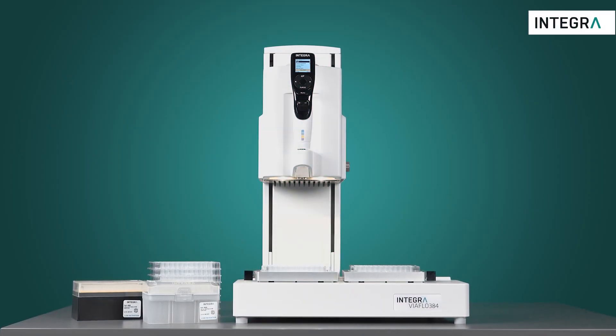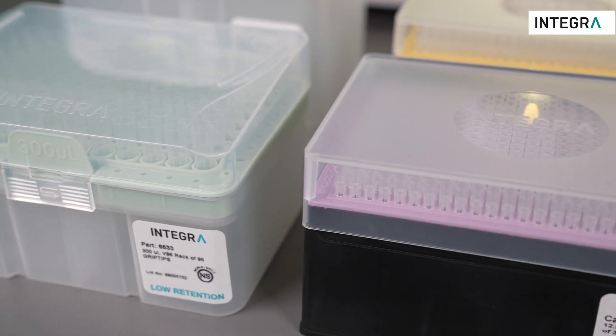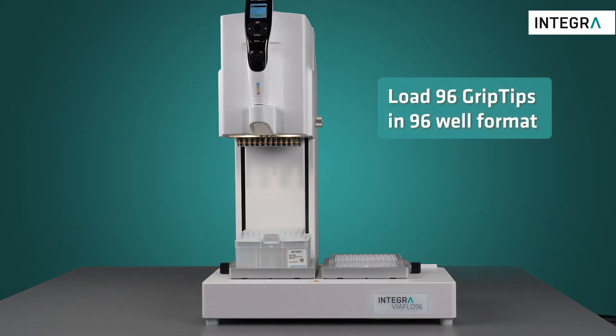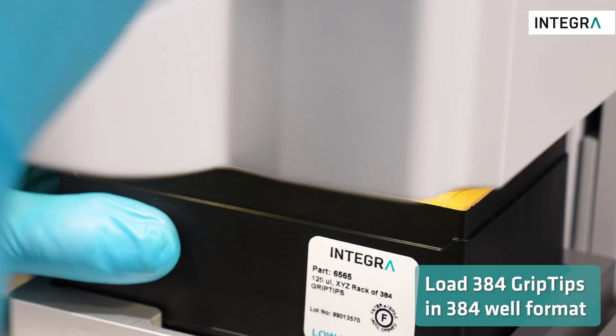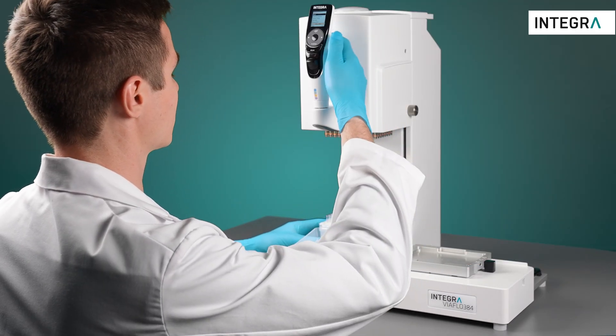The ViaFlo 96 and ViaFlo 384 have been designed to work with grip tips, which are guaranteed not to leak or fall off. To load 96 grip tips in 96-well formats, or to load 384 grip tips using a 384-channel head, place the tip rack on any plate holder and move the pipetting head straight down into the tips.